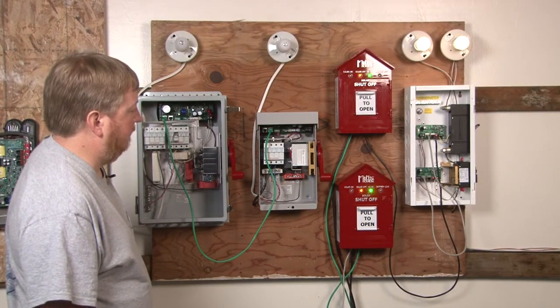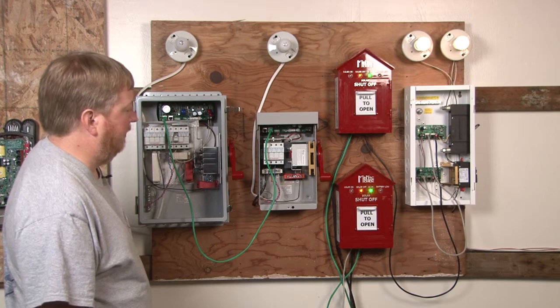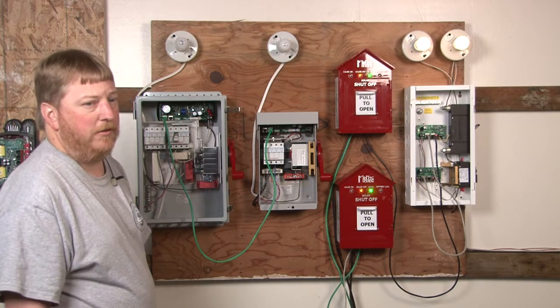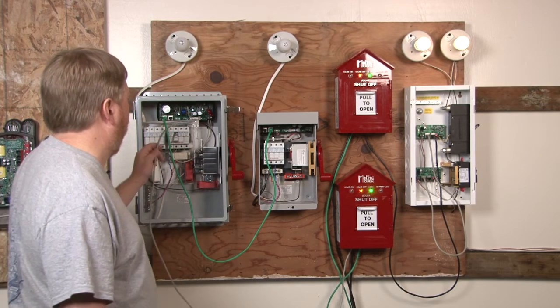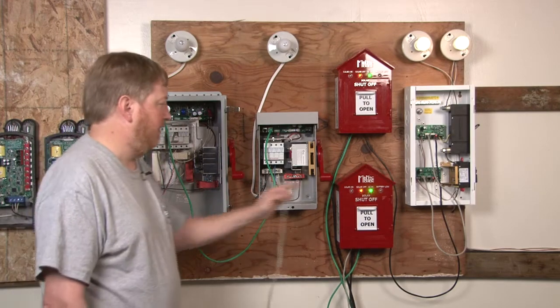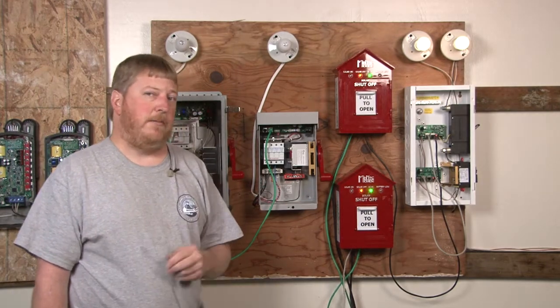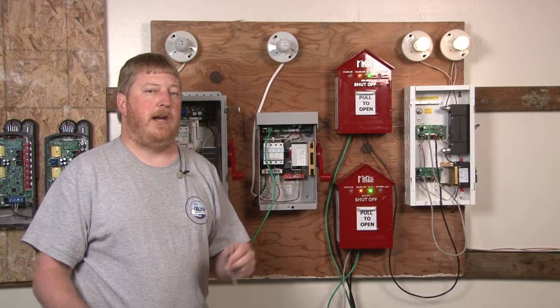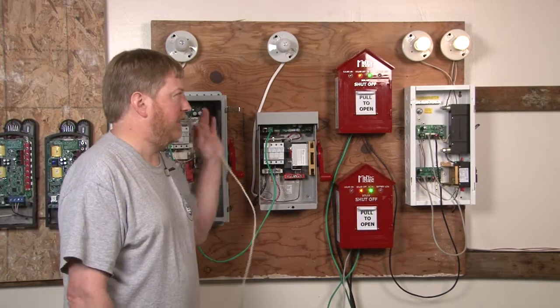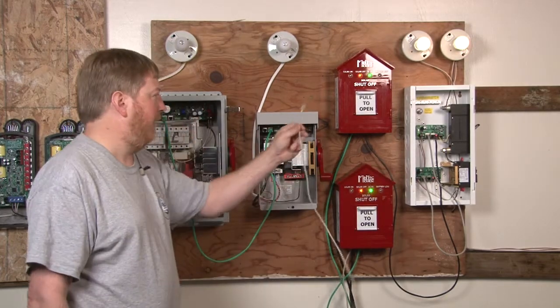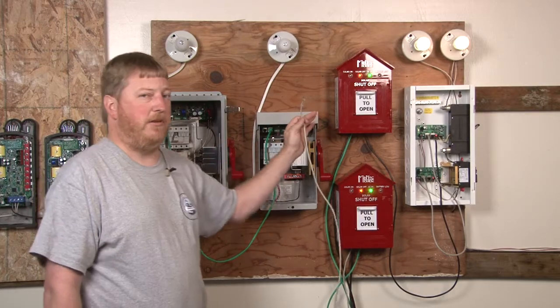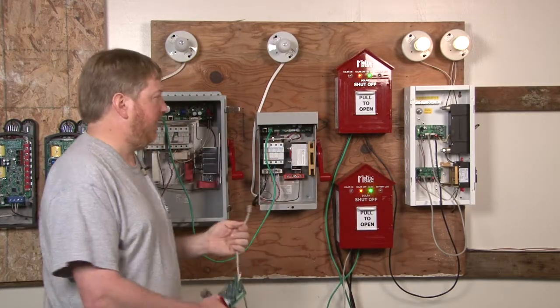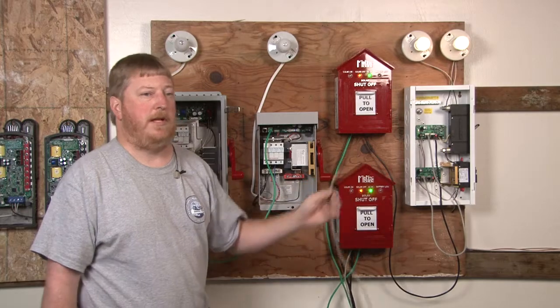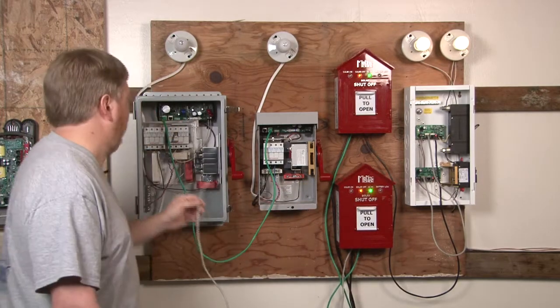As you can see there, it shut off the combiner boxes because we damaged the cable going to those combiner boxes. If the cable is unplugged, it's just going to shut the system down. If the cable is actually damaged by a fire or a mouse, we'll say, it'll shut the whole system down. So as you can see, I unplugged the cable, so it only shut down what's upstream of the cable. If I'd actually cut the cable, it would shut the whole system down, and then it would give us a warning the cable is damaged.